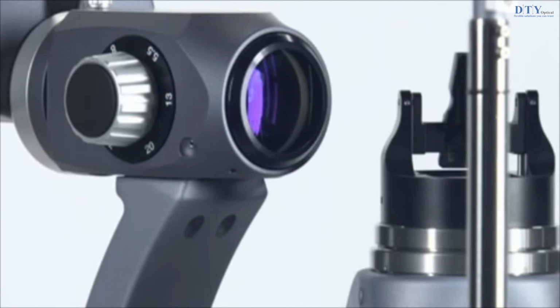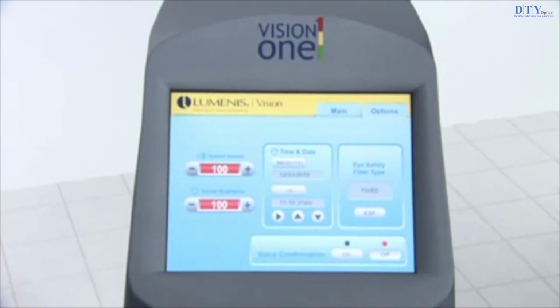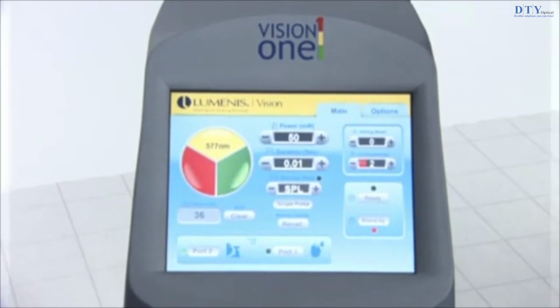If the electronic system detects a fault condition, the laser exposure cannot occur. The laser power supply is turned off, the safety shutter is closed, and the foot switch is disabled. Some fault conditions may be cleared by the operator. Refer to the troubleshooting guide in your operator's manual for additional information.